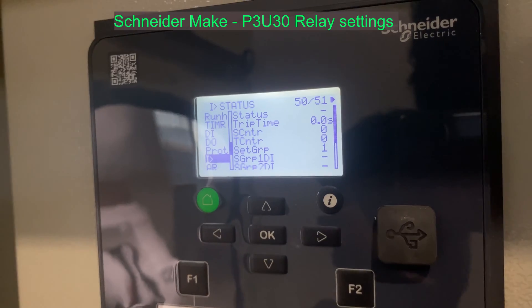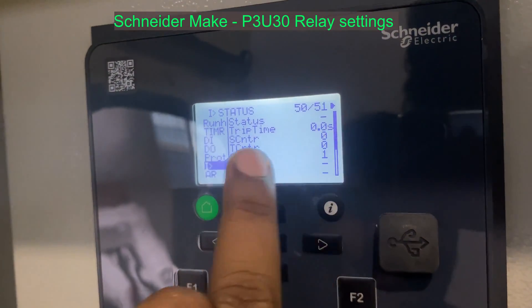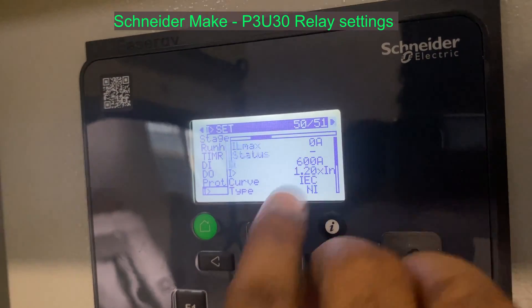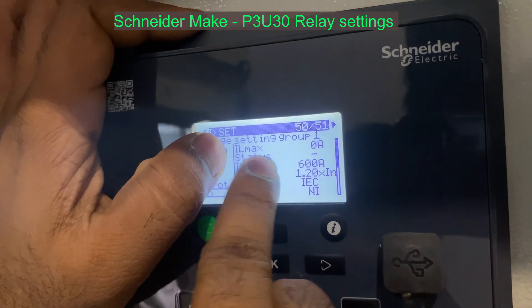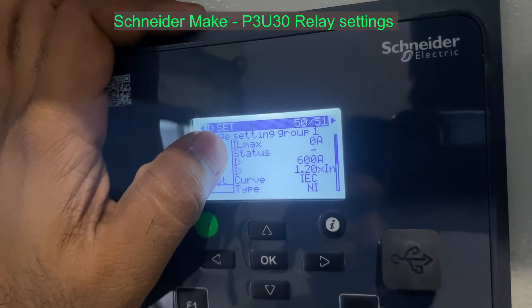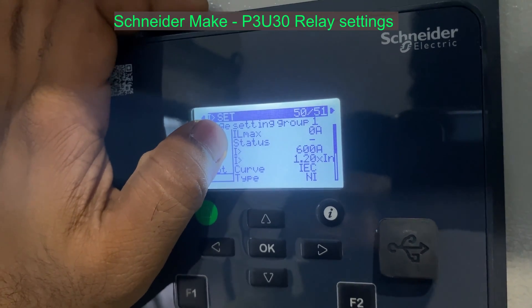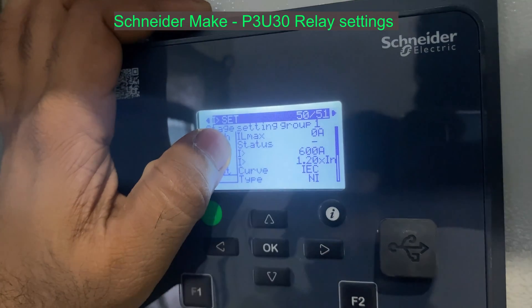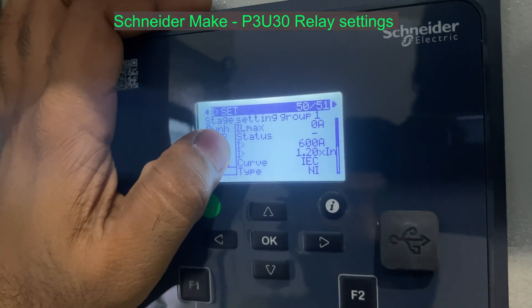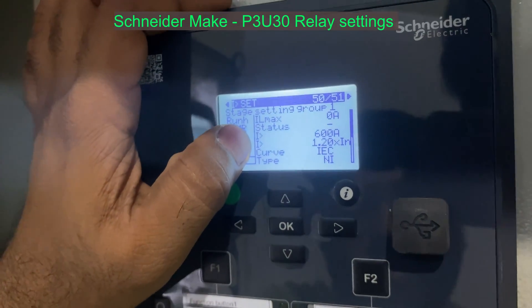We are going to overcurrent — overcurrent shows the status of trip time. Here is the fault status. We are going to measure IL maximum for R-phase, Y-phase, B-phase — where there is a maximum RMS current status, whether it is start or fault. We are going to set the set point to 600 amps — that is 1.20 times 500 amps. We will set the default to 500 amps.